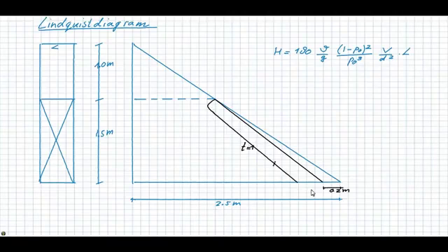Note that at the bottom part of the filter the line is parallel to the clean bed pressure line, because in that part the filter is still clean. Theoretically, we can continue until the pressure line touches the y-axis. There the pressure in the filter is equal to the atmospheric pressure.